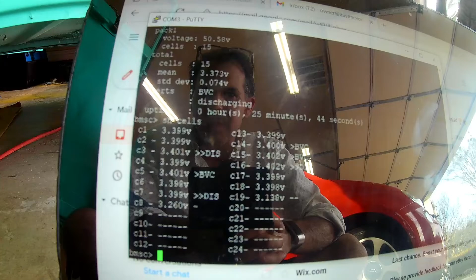Finally, let's review what I set the voltage safe range to be in our battery management system, BMS. The configuration consists of first the low voltage alarm, or LVC, which triggers if any single cell falls below 2.8 volts. The next one, high voltage alarm, or HVC, triggers if any single cell charges above 3.6 volts.